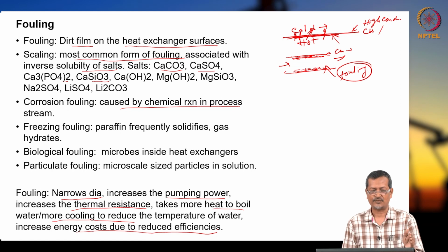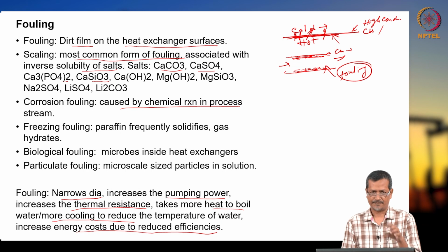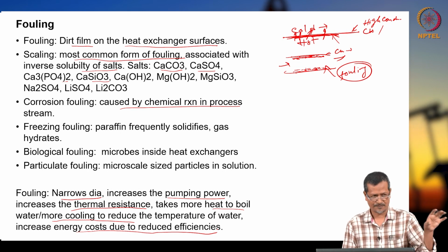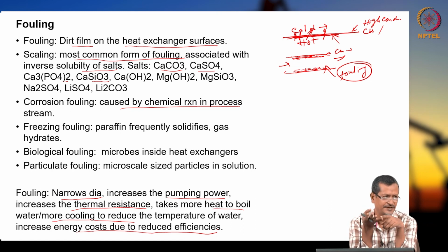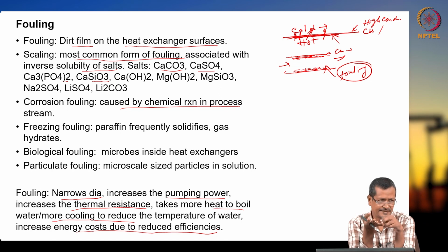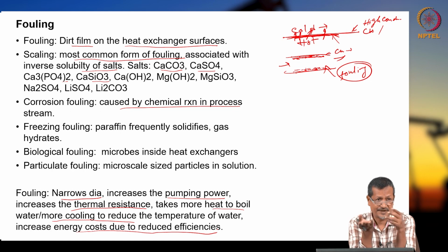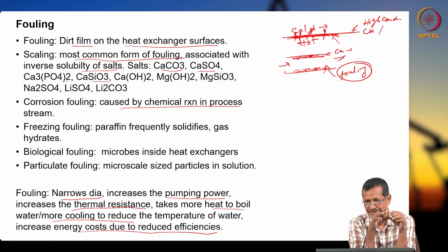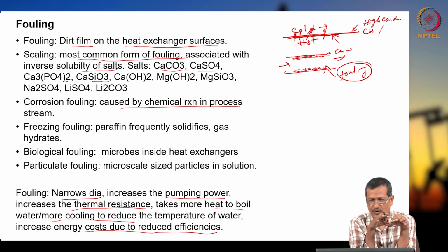Okay, so fouling, you have to consider whenever any piping system is there. Because oil and gas industry means lots of piping systems. So in the piping system you have to check all these things. Actually for fouling you have to check any erosion, corrosion, any dirt getting deposited, any sand getting deposited, any hydrogen sulfide or other corrosive material. So again you have to check whether that is creating corrosion and fouling or any other leakage. Okay, so all these things you have to observe.